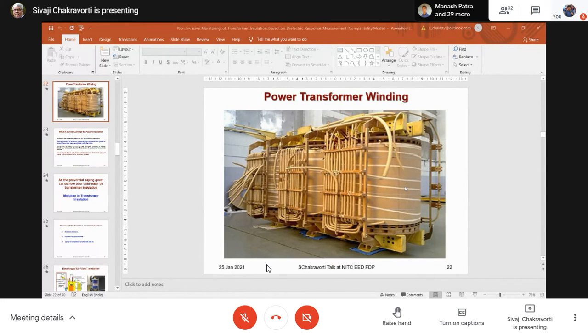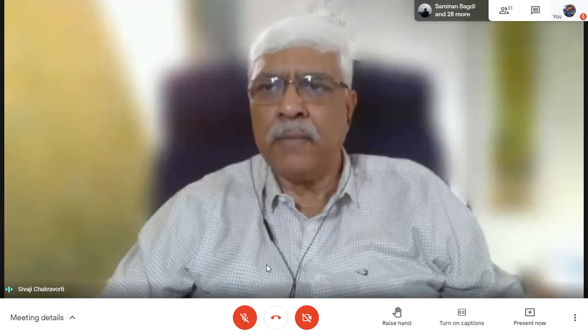This is the first question, that how do I make it? I mean, physically, how do I make it? How do I take the conductor? How do I connect? And the second point is the second section potential is not equal to the first section, not equal to the third section. There is a big difference. So the interleaved connection, making the connection is a big issue.